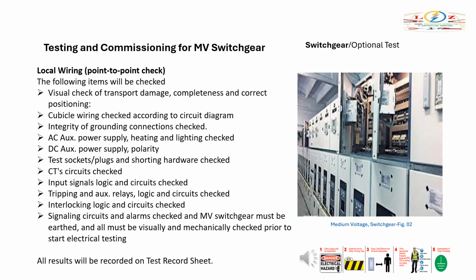CT circuits checked. Input signals logic and circuits checked. Tripping and auxiliary relays, logic and circuits checked. Interlocking logic and circuits checked. Signaling circuits and alarms checked, and MV switchgear must be earthed. And all must be visually and mechanically checked prior to starting electrical testing. All results will be recorded on the test record sheet.